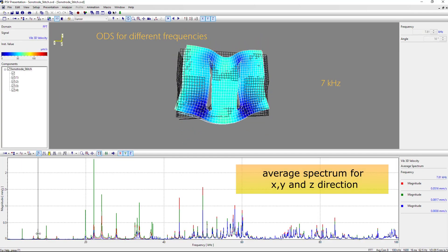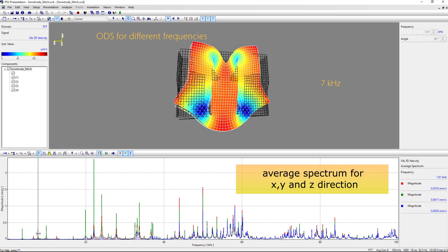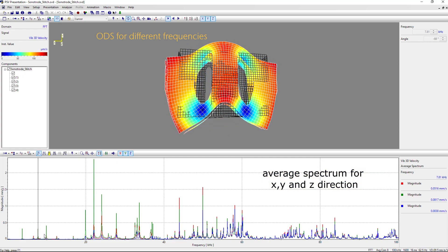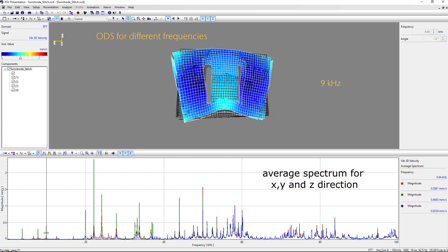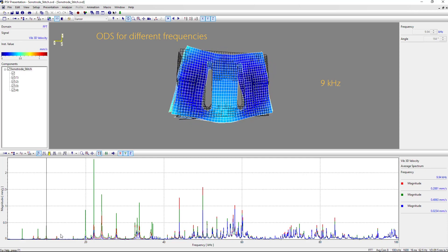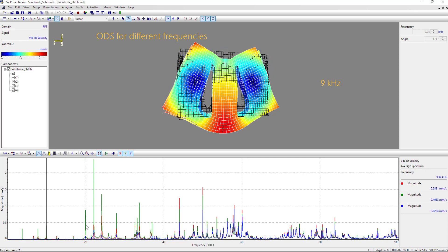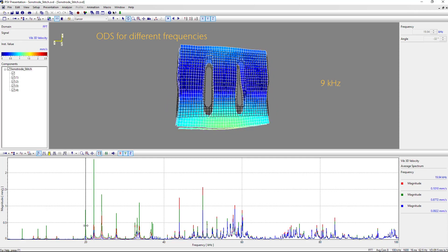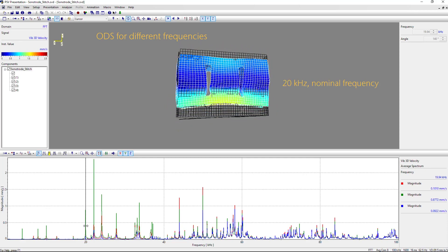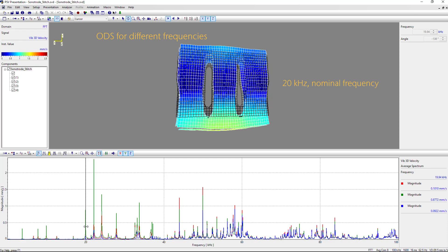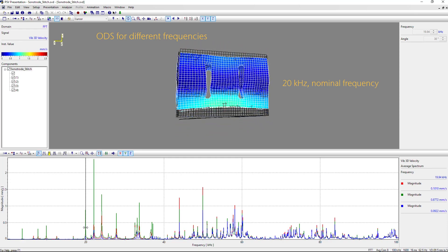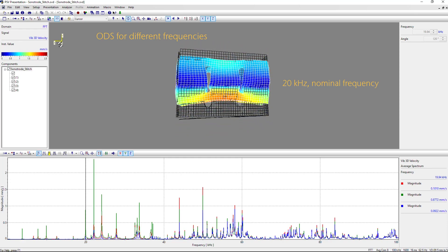Now we look at the operational deflection shapes for the different frequencies. Here, the lower frequencies are bending modes. If you go to the nominal welding frequency, which is 20 kHz, it shows a piston mode.